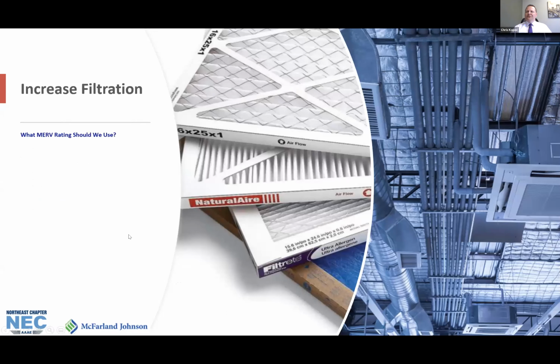So what's the best MERV rating for your equipment? HEPA filter sounds pretty good, so why don't we just add HEPA filters to all our equipment? Well, it doesn't really work that way. So your building's central air handling equipment is going to have the greatest potential to take advantage of the filter upgrade. The internal fans are more powerful and can handle more efficient filters, and they're much better than the smaller decentralized equipment that requires filters. This is because increased filter efficiency generally requires an increased pressure drop through the filter. So in simple terms, a pressure drop is basically air resistance.